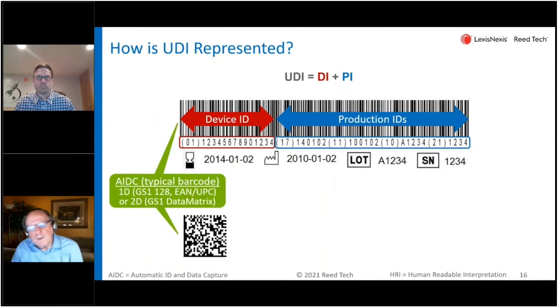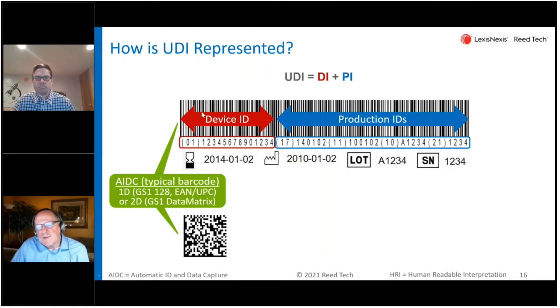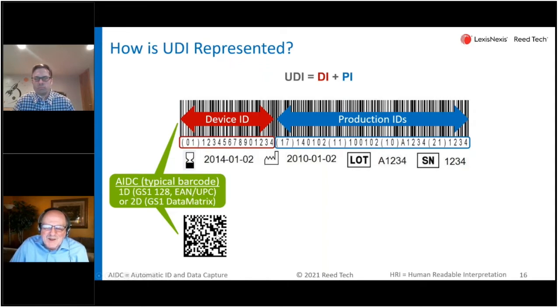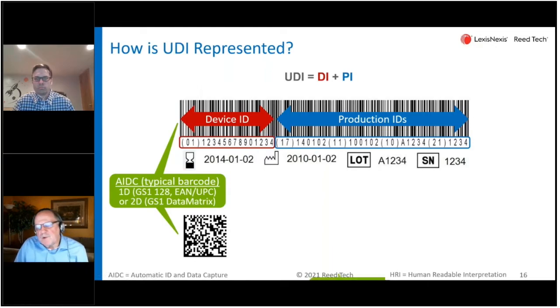How is UDI represented? It is represented in what regulators refer to as AIDC, or what standards organizations call automatic identification and data capture. That typically manifests as a linear barcode or, more attractive and desirable these days, a two-dimensional barcode. It uses less real estate and you can pack a lot more information into it, so it has definite benefits. Typically either a one-dimensional or two-dimensional barcode.